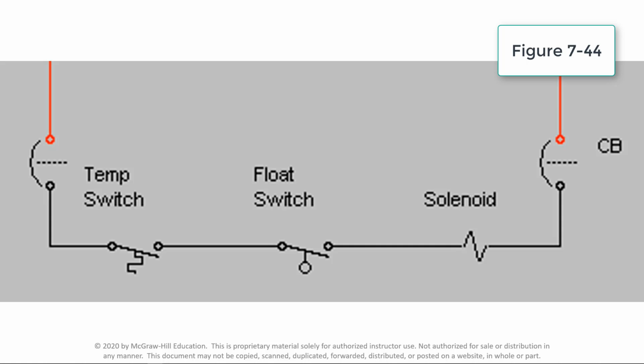This video demonstrates the operation of an AND logic function. Logic is the ability to make decisions when one or more different factors must be taken into consideration. Control logic functions describe how inputs interact with each other to control the outputs. The AND logic function operates like a series circuit. AND logic is used when two or more inputs are connected in series and they all must be closed in order to energize the output load. In this application, both the temperature switch and the float switch inputs must be closed to energize the solenoid output.